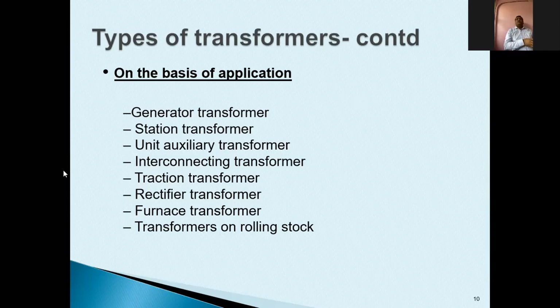Then to limit the resistance R, what I have in my control is the cross-section area of that conductor. So I use a lower current density when I am going for generator transformers. When I have a lower current density, then my cross-section area will be very high. If I keep 2 ampere per mm square, then to carry the current of 20,000 ampere, I will need the cross-section area of that conductor to be 10,000 square mm.